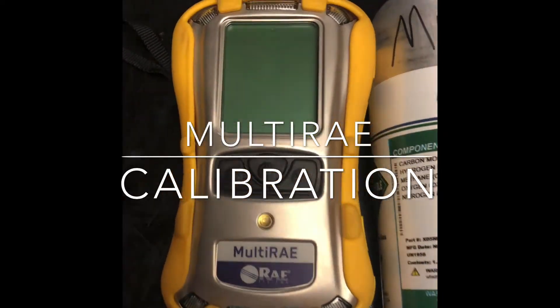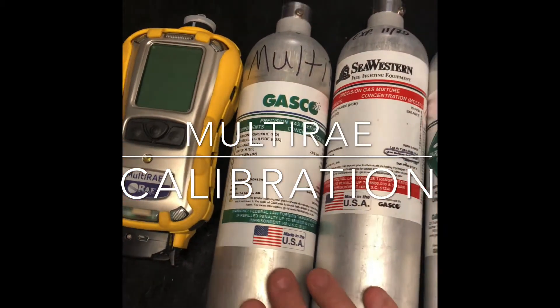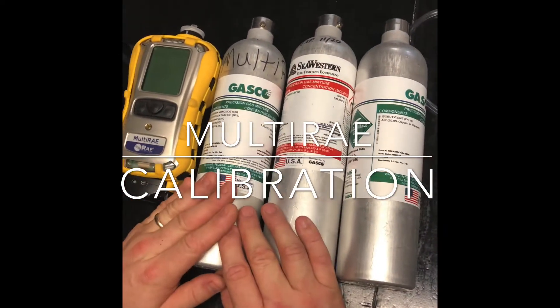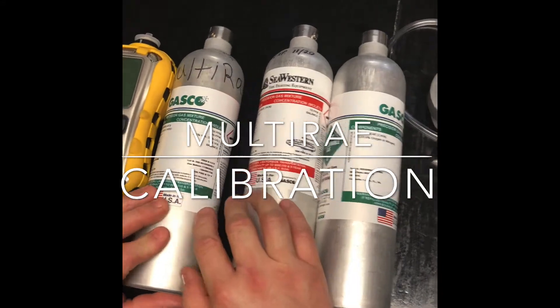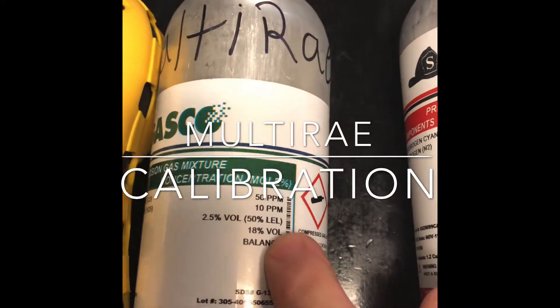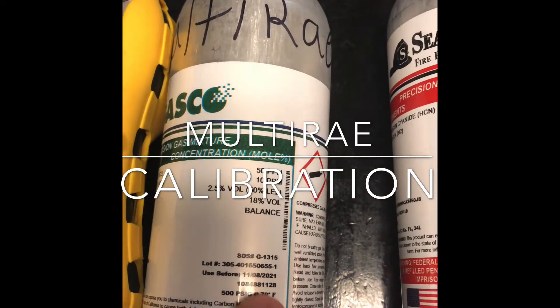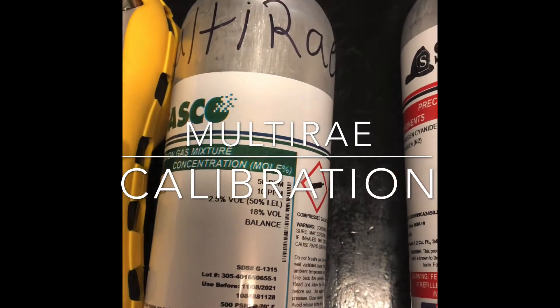We're going to talk today about bumping and calibrating the MultiRAE. Things you're going to need: your MultiRAE, your 4-gas mix, and you want to make sure that you are at methane 2.5% volume, 50% LEL. Like I said in the earlier videos, you always want to check your use before — make sure your gas is current and up-to-date.